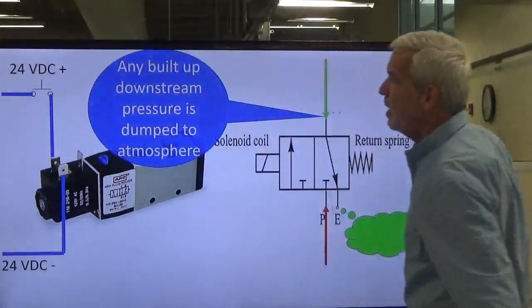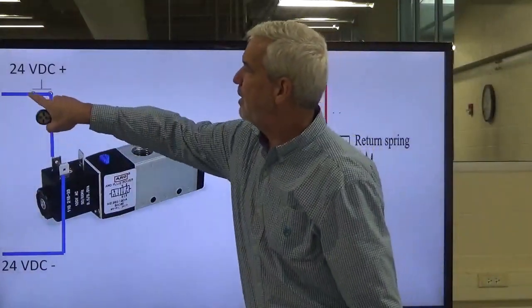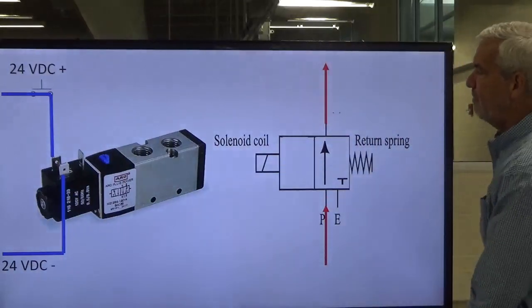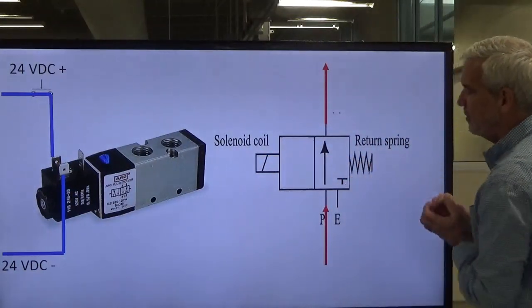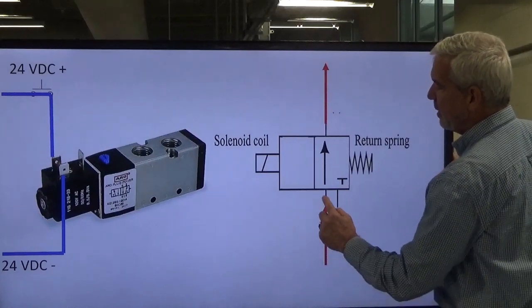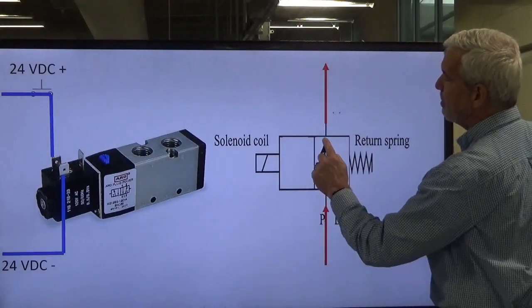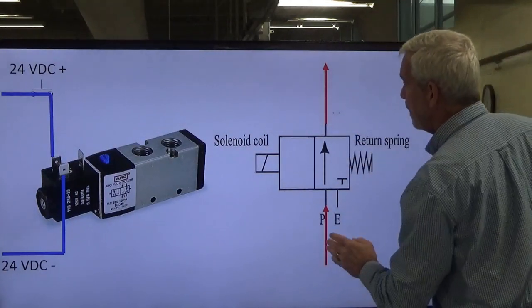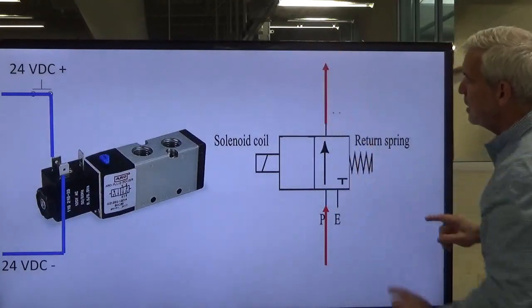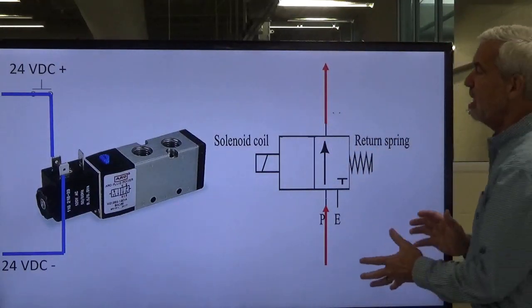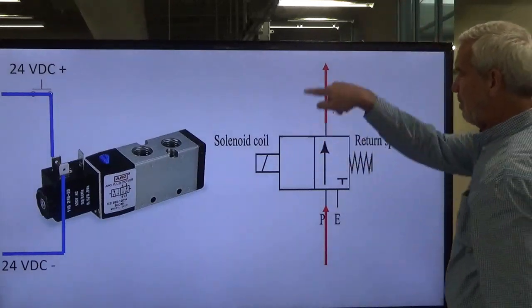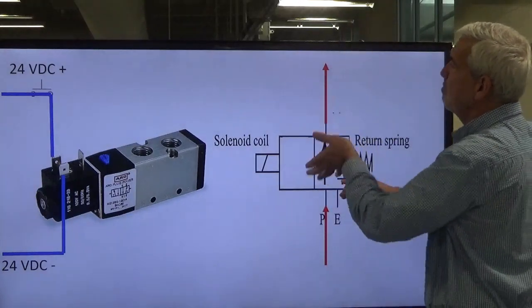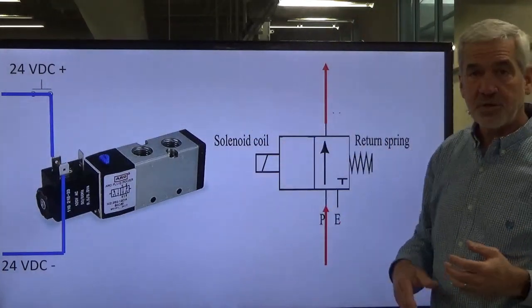When I press my push button and provide a path for voltage to energize the coil, that magnetic field shifts that valve. When it shifts, now the spool is allowing air to pass through to our downstream system. Notice there is no pathway to exhaust - we're capturing and trapping all that air and moving it in our system. All of our system pressure is going to all the components we're trying to control.